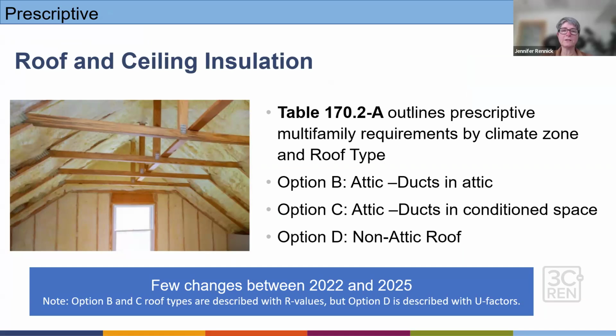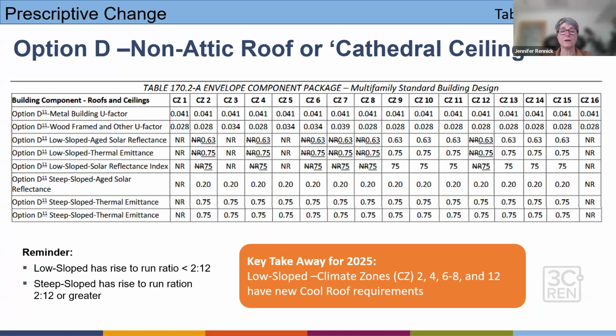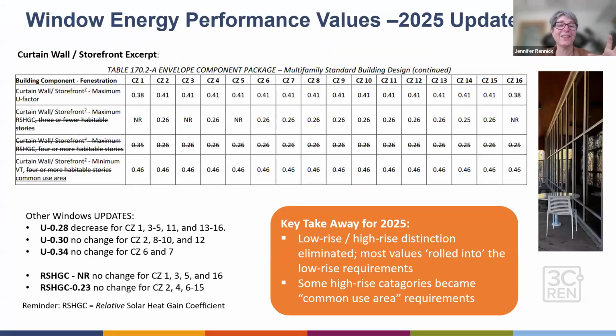So roof and ceiling insulation, just as a reminder, option B is an attic with ducts in the attic. Option C is an attic with ducts in the conditioned space, and option D is a non-attic roof or cathedral ceiling. Basically there's hardly any changes for options B and C, but there was some change for option D. The main takeaway is that when you have a cathedral ceiling or non-attic roof for climate zones 2, 4, 6, 7, 8, and 12, now a low sloped roof has some cool roof requirements. And that's basically it. Now we're done with envelope, except for the windows. Not a whole lot has changed there. And then on the window performance values, there are some updates.